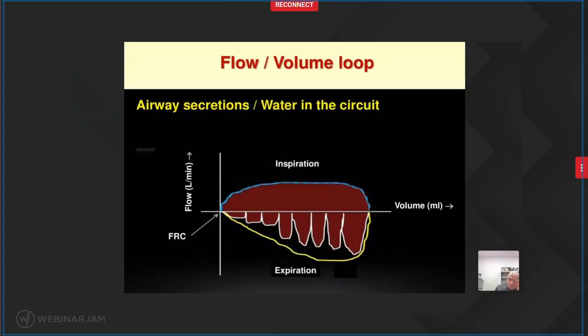restriction. Okay, this is another example of an abnormal volume flow loop. As you can see here, the yellow line is supposed to be the normal expiratory flow, but you can see here this line is quite abnormal, quite uneven, quite unequal. And this is usually because there's something on the expiratory limb that is causing these changes in flow. The most likely reason for this is either secretions or water in the circuit.